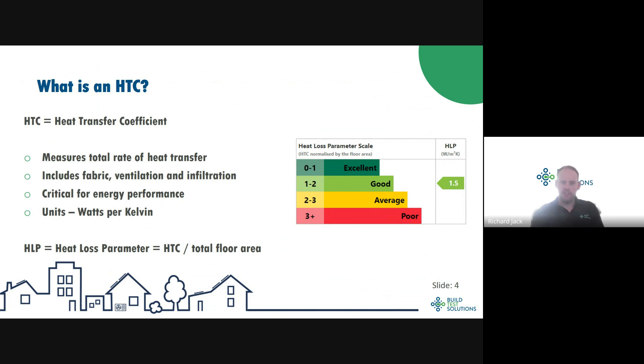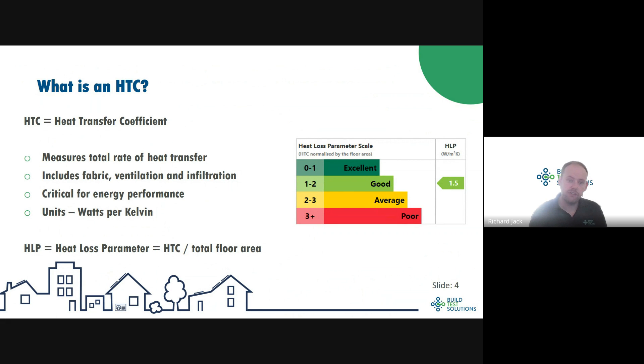So what is the HTC? The HTC is the heat transfer coefficient, and it's a measurement of the total rate of heat transfer between inside and outside your house. It includes all sources of heat transfer: through the fabric — meaning through the floor, walls, windows, doors, and ceiling — by ventilation, which is deliberate air movement, and by infiltration, which is accidental air movement through the building fabric.